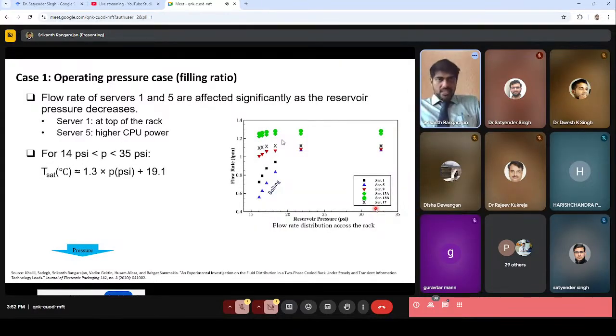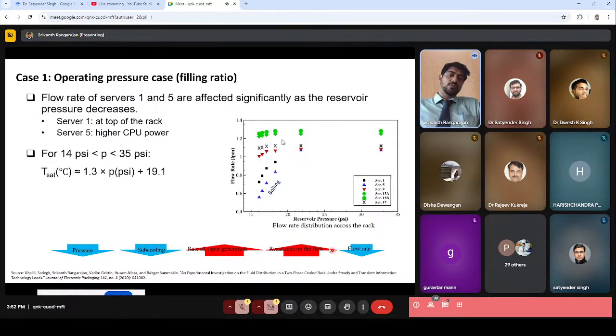So here, if I don't apply any heat, you can see that the flow rates of servers 1 and 5 are affected significantly as the reservoir pressure decreases. As the pressure decreases, the subcooling decreases, the rate of vapor generation increases, and because of that the resistance to the flow increases and the flow rate decreases. As the subcooling decreases, we are closer to the saturation condition. Because the fluid enters the cold plate at the saturation condition, it picks up the heat readily, and there is a lot of vapor generation. The generated vapor causes a resistance to the flow because of the friction between the generated vapor and the liquid pool, because of which the flow rate reduces, since the pumping power is kept constant. So the flow rate will reduce to tackle this increase in the resistance.